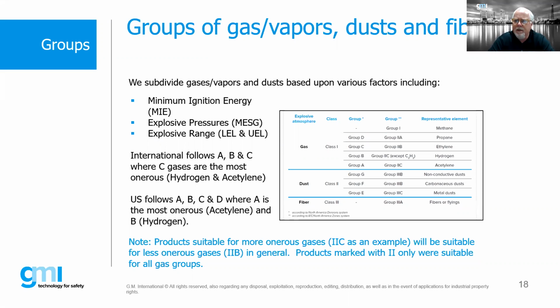So there used to be, and you will still find, products that are marked with just a Roman numeral. If it's marked with a Roman numeral 2, then it was implied that it was good for all gas groups. Now, the latest edition of the 60079 standards insists that products that were previously marked as Roman numeral 2 shall now be marked Roman numeral 2C. So understand that gases get grouped into different groups based upon various factors. In the United States, we follow a similar concept, except the letters don't jive with the international community. Of course, we have to be a little bit different.